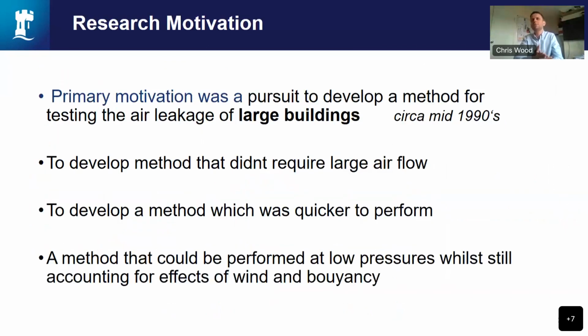So what is our motivation? The primary motivation, going back to the thoughts of David Etheridge in the 1990s, was a pursuit to develop a method for testing the air leakage of large buildings. If we think about that relationship between leakage and pressure difference, as we go to increasingly large, increasingly leaky buildings, we're going to require much larger airflow.